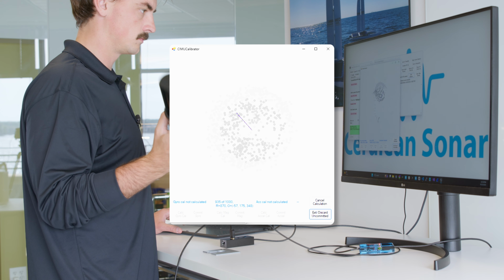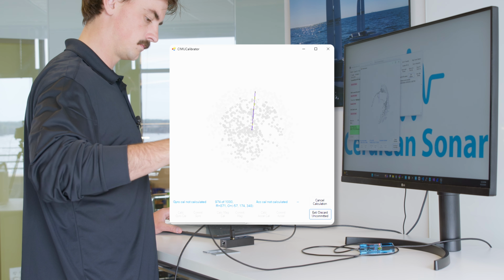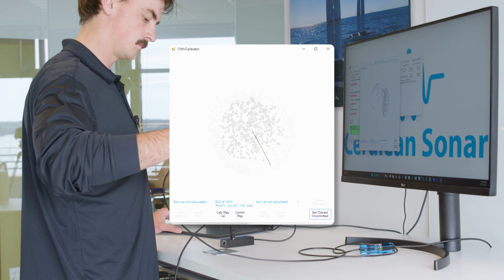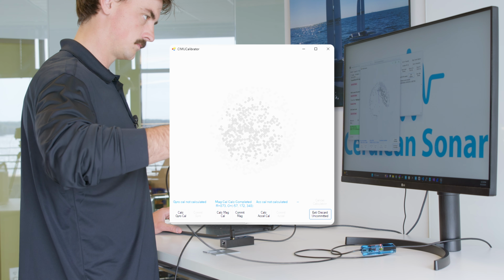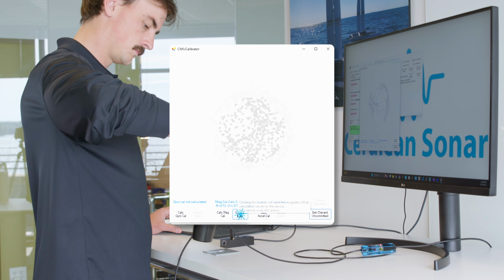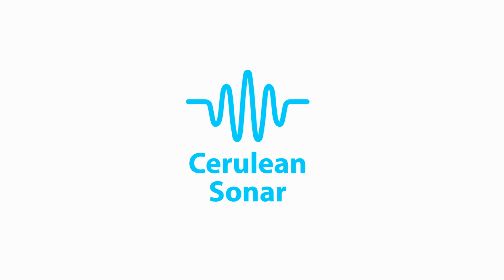Once 1,000 points have been collected, the system will stop recording. If the points appear evenly distributed, click the Commit Mag button to complete the calibration. If not, you can click the Calc Mag Cal button to retry.